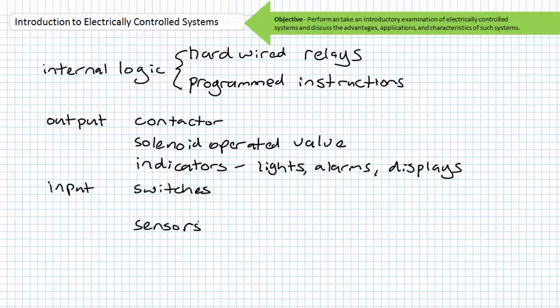On the input side of an electrically controlled system, these devices can again be thought of as the eyes and ears of a system that acquire data about the outside world. Input devices ordinarily take the form of switches or sensors. Switches are different than sensors, and the primary distinction is that of digital versus analog nature of the two. Switches are discrete and clear in nature and can be in one of two mutually exclusive positions, either closed or open, and never a little bit of both or halfway in between.